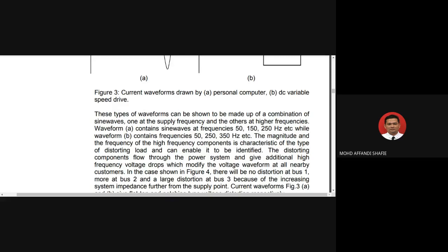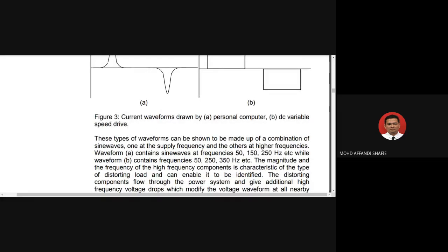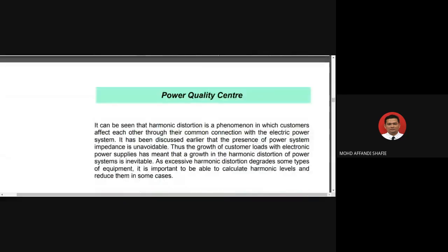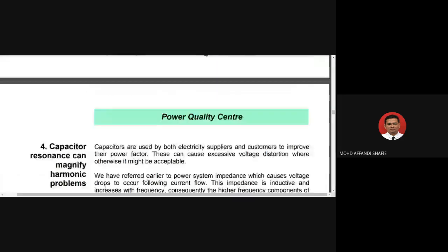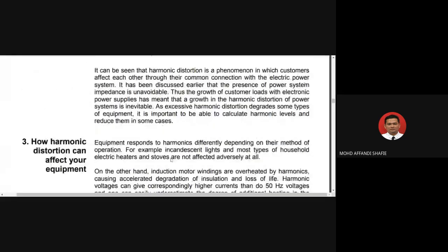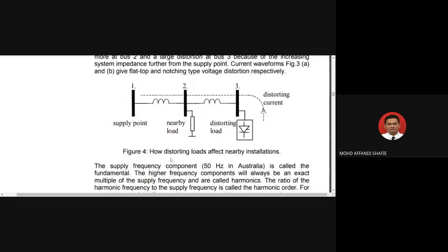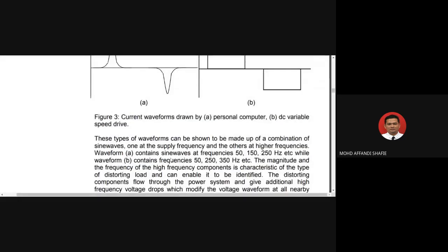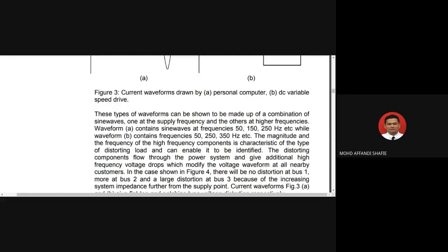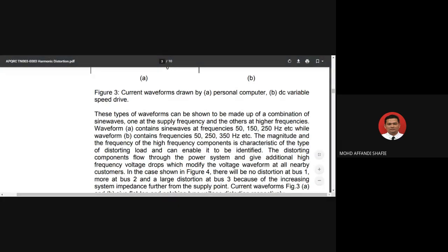So waveform A contains sine waves. Which figure are you referring to? Figure 3A. Waveform A contains sine waves at frequencies 50, 150, 250 Hz and so on, while waveform B contains frequencies 50, 250, 350 Hz and so on. The magnitude and the frequency of the high frequency components are characteristic of the type of distorting load and can enable it to be identified.